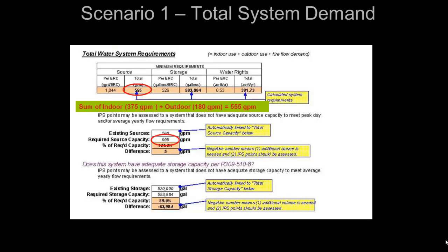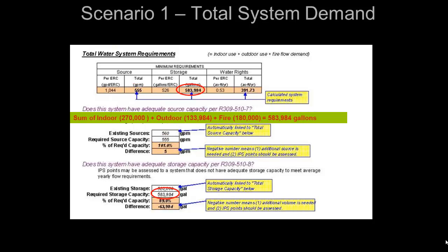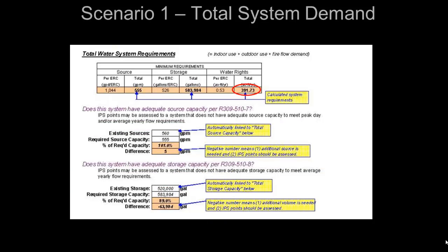Source capacity is calculated by adding the indoor and outdoor demands for a total of 555 gallons per minute. Storage capacity is calculated by adding the indoor, outdoor, and fire demand requirements for a total of 583,984 gallons. Water right requirements are also totaled to verify that the system has sufficient water rights. The spreadsheet will then help us determine if the system has adequate source and storage capacity. In this example, this system has just enough source capacity but is lacking or deficient in the needed storage volume — short by about 64,000 gallons. This deficiency for lacking proper storage capacity will need to be documented in the Electronic Sanitary Survey Program.